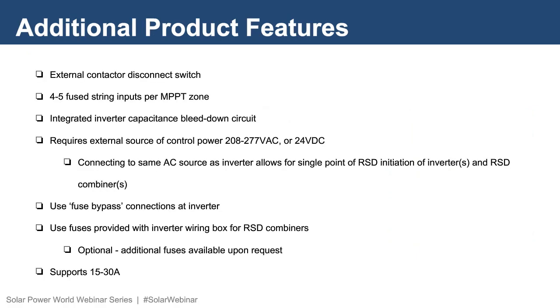Additional features of the RSD combiner worth highlighting. These products include an external contactor-based disconnect switch. This switch allows you to remotely disconnect the combiner from feeding the PV energy back to the inverter. These combiner boxes are available with different fuse quantities per zone. We can offer these solutions with either 4 or 5 fuses, depending on the array configuration and how many strings of PV source circuits you have going to the inverter MPPT zone.